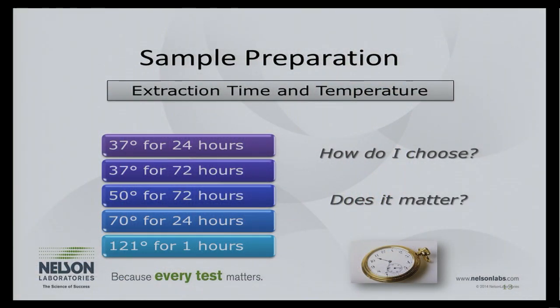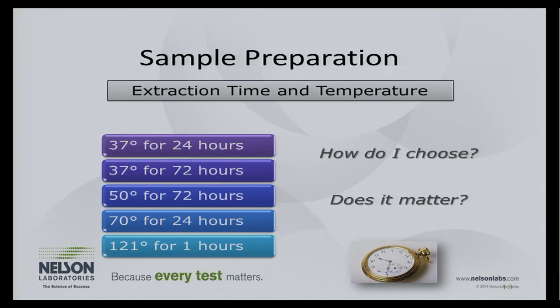Once we know how much fluid to extract the device in, we need to decide the extraction temperature and duration. The options from ISO 10993 are: 37°C for 24 hours (cytotoxicity only), 37°C for 72 hours, 50°C for 72 hours, 70°C for 24 hours, or 121°C for one hour. Many people want to choose 37°C because that's body temperature, but if your device has contact with the body longer than 72 hours, we recommend extracting at 50°C to get a more exhaustive, long-term extraction.